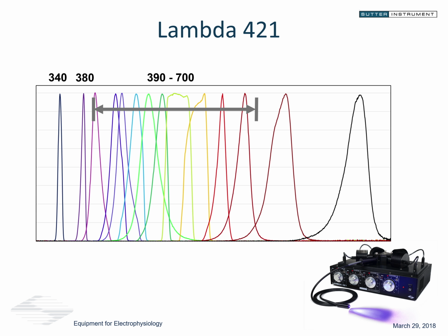Now, there's been 340 LEDs available for some time. However, in order to use them in a microscope for fluorescence work, for example, you need a very powerful LED. And I would say that this is the first time that we've had LEDs that are truly powerful to do experiments such as Fura experiments, for example, with reasonable exposure times. And in fact, now the new series of LEDs at 340 and 380 are quite bright, and you can actually turn them down and still get very good excitation and exposure times.